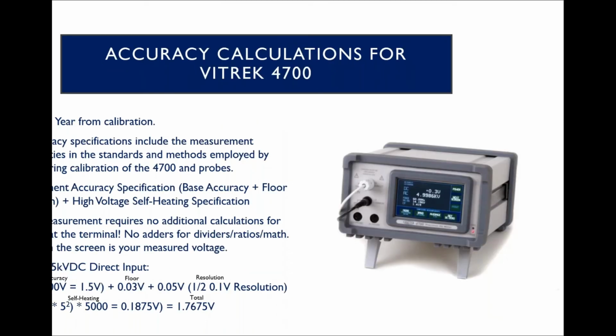So I'd like to go through and show you how easy it is to calculate the accuracy for the 4700 using our published specifications. So our accuracies are valid for 1 year from calibration. The accuracy specifications include the measurement uncertainties in the standards and methods that we use in our labs here for every single 4700 calibration. So really the calculation is going to be a combination of the base accuracy of the product that we specify, along with the floor and the resolution. And then there's a high voltage self-heating adder as well.